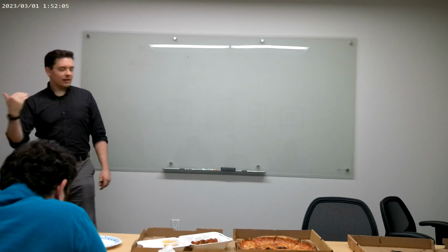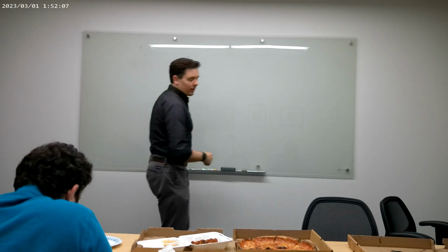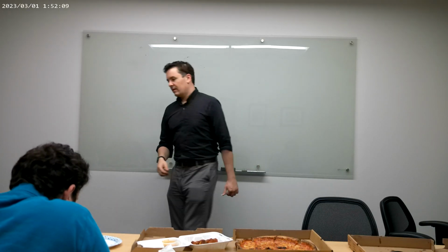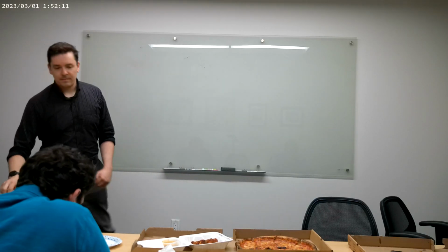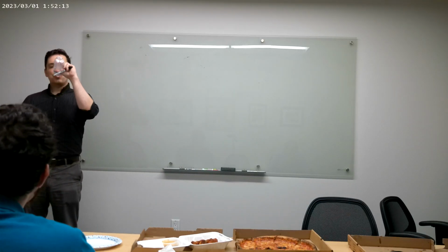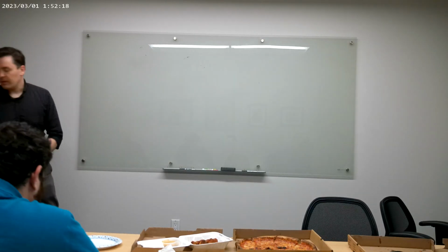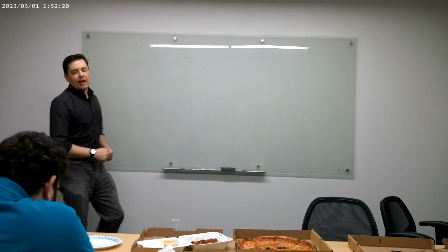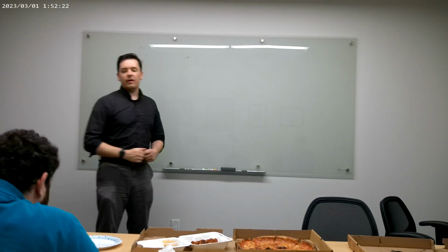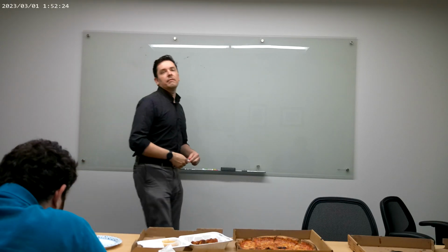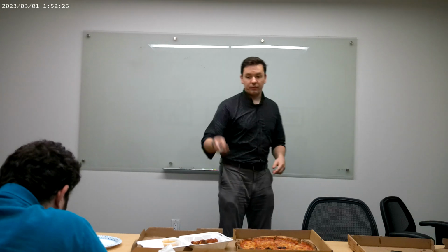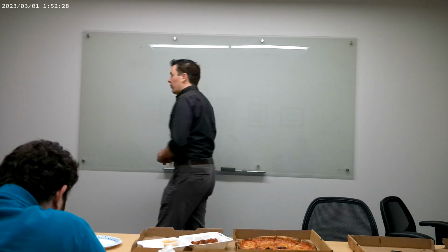Tom, read me out. What's the heading of table 100.1? Insulation resistance test values. There you go. Electrical apparatus and systems other than rotating machinery. All right. So you are going to test a medium voltage circuit breaker. Let's say it came out of a 15 kV system. So first of all, tell me what your test voltage is.